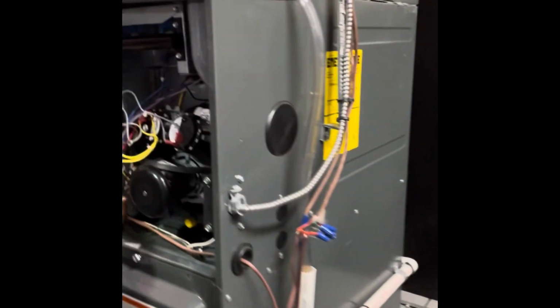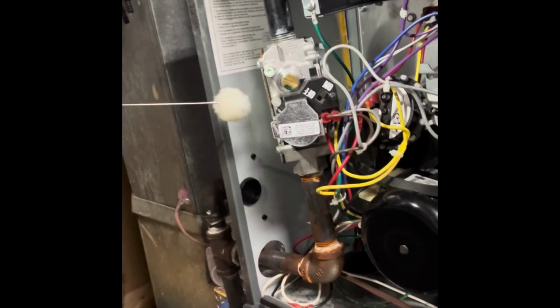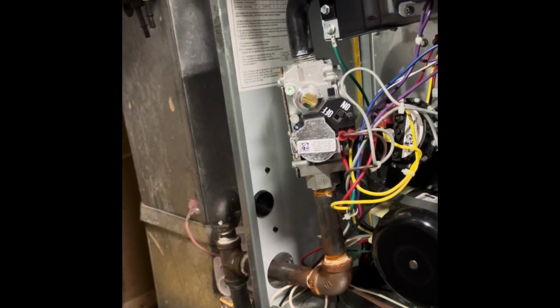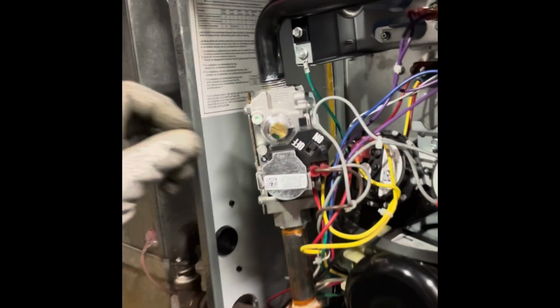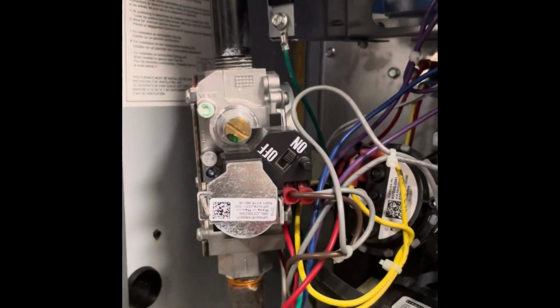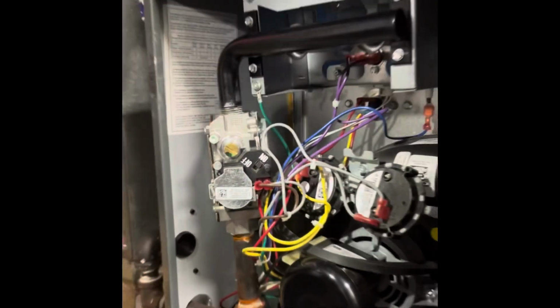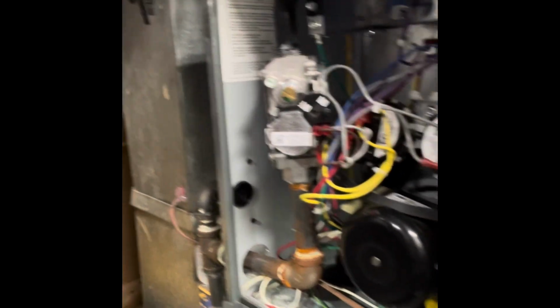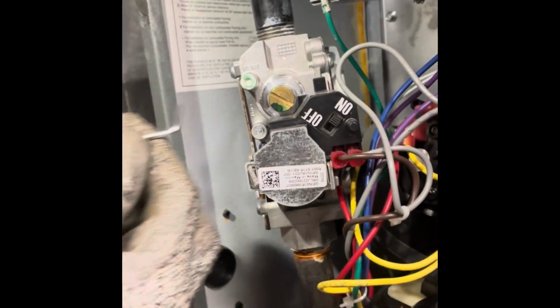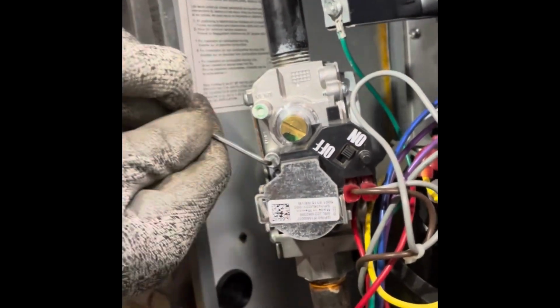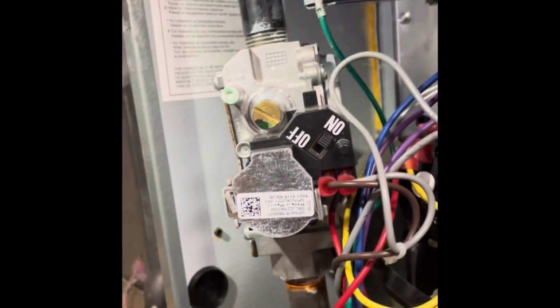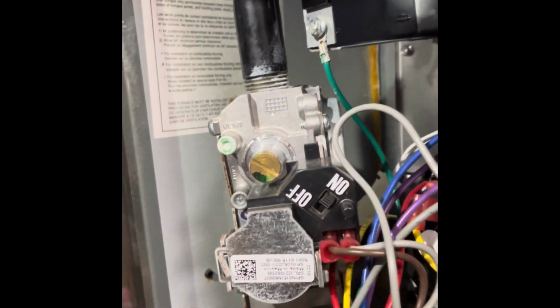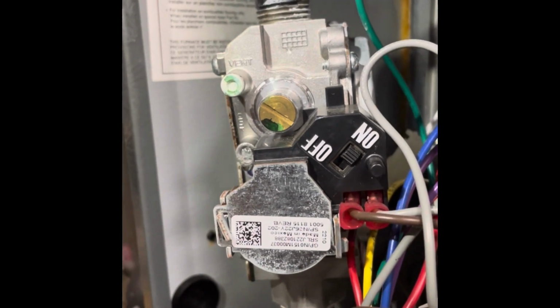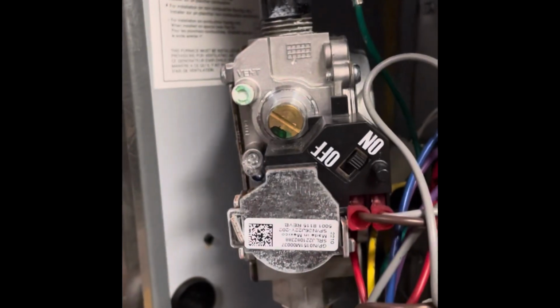So we've got our burners lit, nice blue flames there. I'm going to soap up the fitting, and we got to see if there's any leaks here. So again, if we had a leak, it would be literally blowing up bubbles. So what I'm going to do, I'm going to just replicate what a leak looks like. And that way you guys can see how we get indication on the leak if we're at a fault. So I'm just going to back this off just a sliver. So if I were to soap this, right now this is leaking. You can actually see that bubble there. That indicates we've got a gas leak.